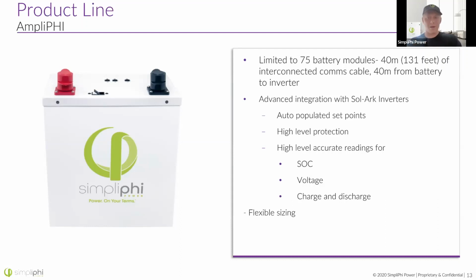Another thing we're going to talk about a little bit today is sizing a battery bank. So with the Phi batteries, with any inverter, you will have some minimum number of batteries that you are required to install to prevent that battery bank from discharging or charging too quickly. With the AmpliPHI battery, you don't have the same limitation. So as long as the AmpliPHI battery is communicating with the equipment, then the equipment's going to know how quickly it can charge the battery.